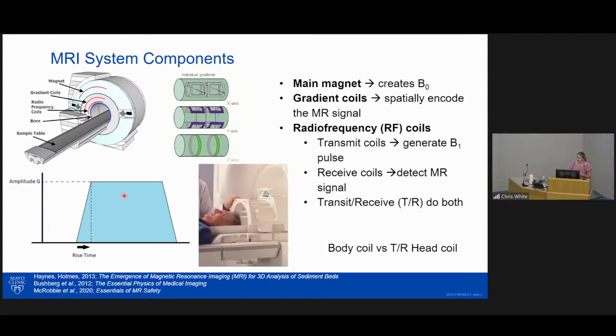And then additionally, I want to explain the difference between a head TR coil and a body coil, as I'm going to use those terms in later slides. So a body coil is built into the scanner, which we can see here, whereas a TR head coil, which is shown here, is something that's plugged into the scanner to allow for localized RF at the head and neck.